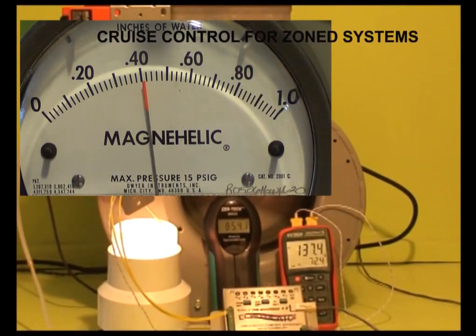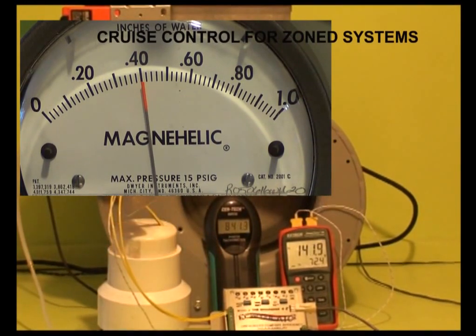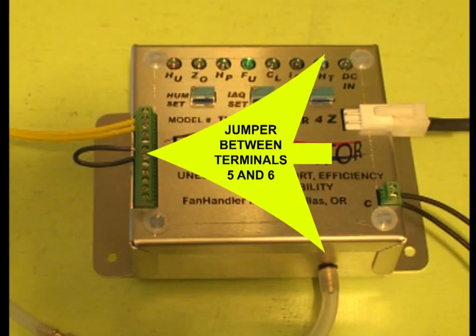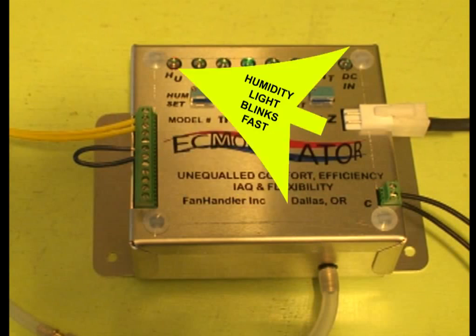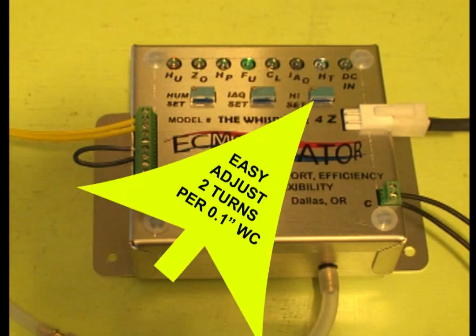Now let's say we don't like 0.4 inches water column for this system. We want, say, 0.2 inches water column. So let's adjust the pressure setting. Start by jumpering between the ECM modulator terminals 5 and 6. The HU humidity light will blink fast.